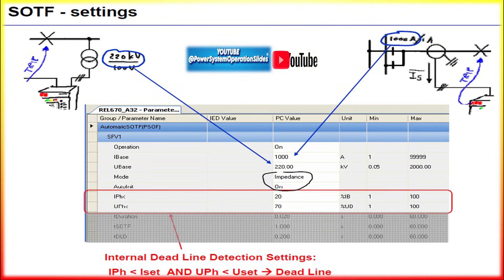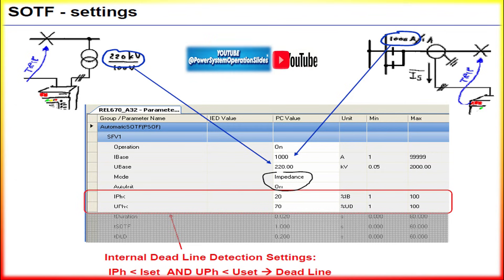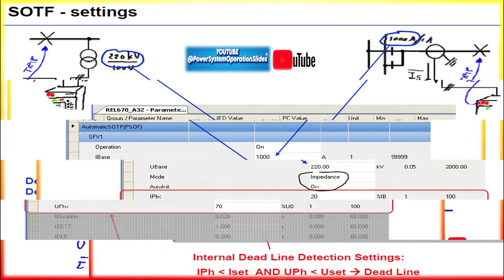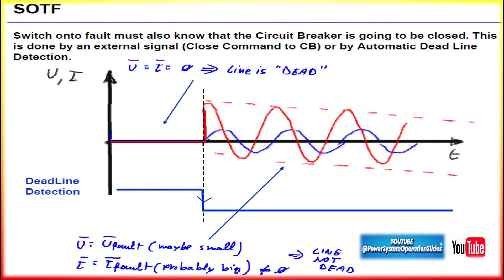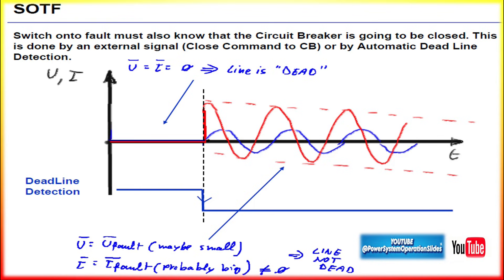The effectiveness of SOTF protection relies on carefully calibrated settings in the IED. Key parameters include voltage supervision (under-voltage detection): the relay continuously monitors the line's voltage before the breaker closes. If the line voltage is significantly lower than the set threshold — typically close to zero — this indicates that the line is de-energized or faulted. For current supervision (overcurrent detection) after the breaker closes, the relay instantly measures the fault current. The threshold should be set high enough to distinguish between normal inrush currents due to charging the line and fault current.